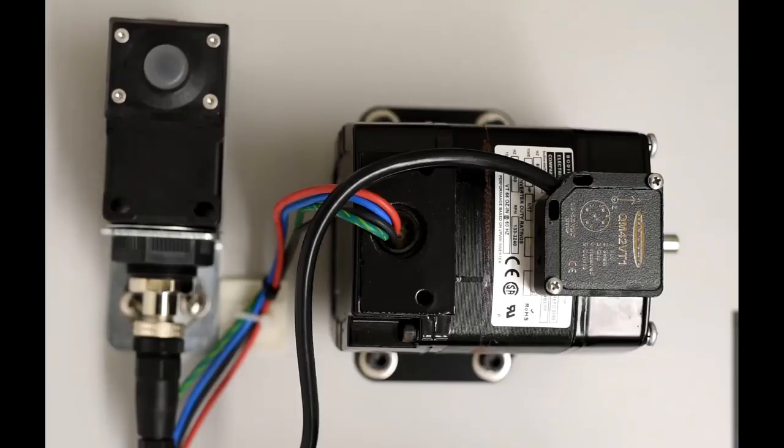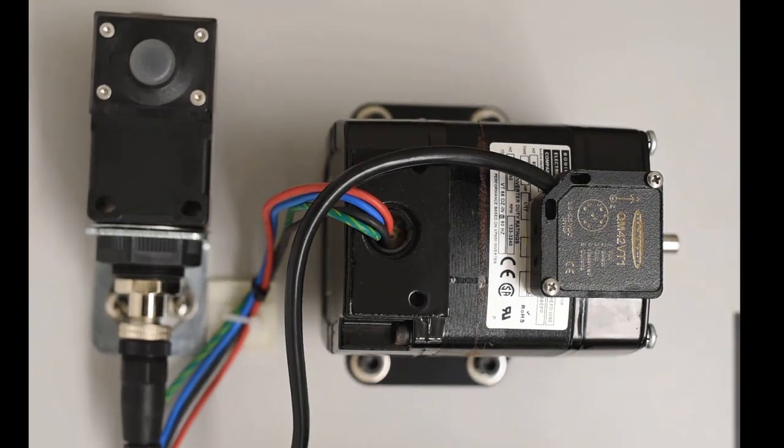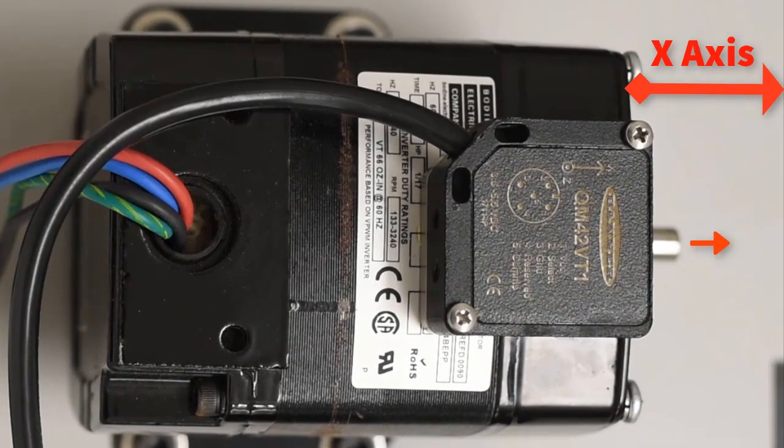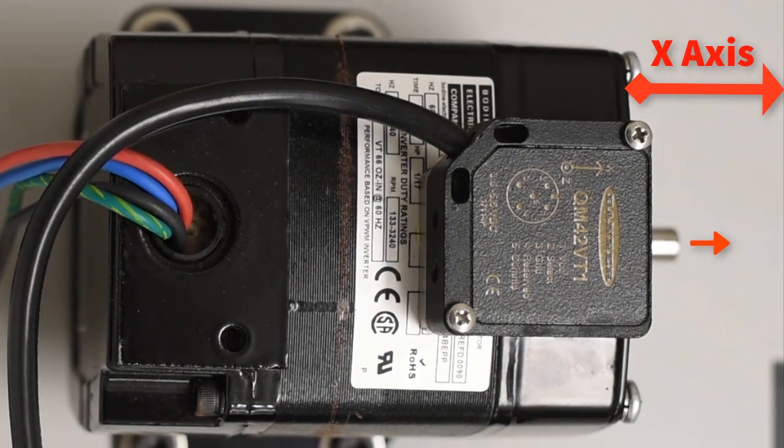Here we're showing you the proper way to connect the vibration and temperature sensor to a motor. Notice the x-axis of the sensor and the shaft should be parallel with each other as shown.